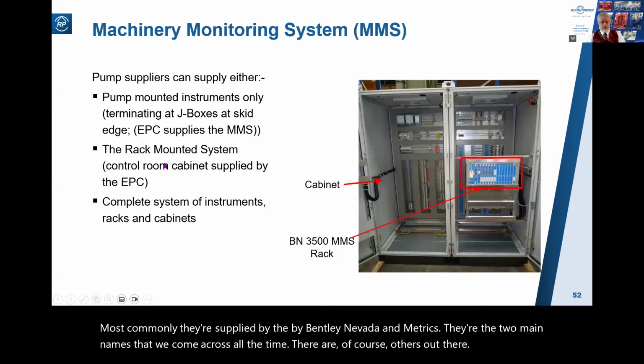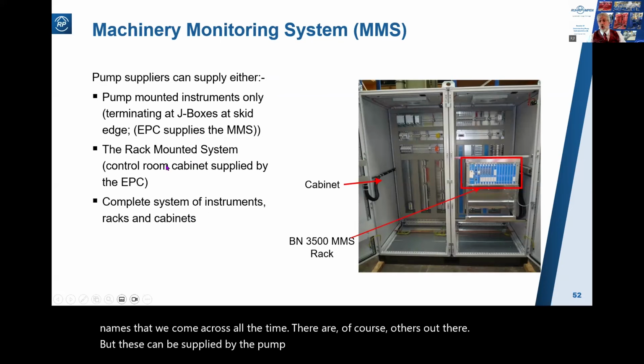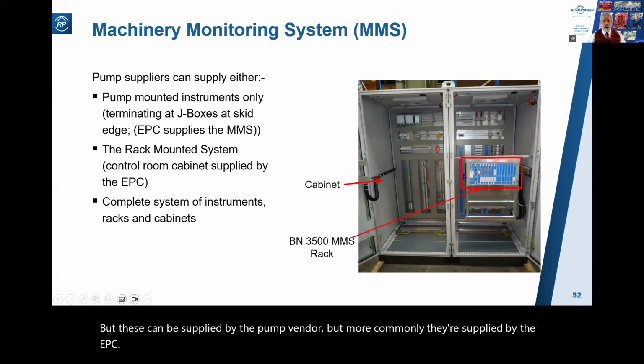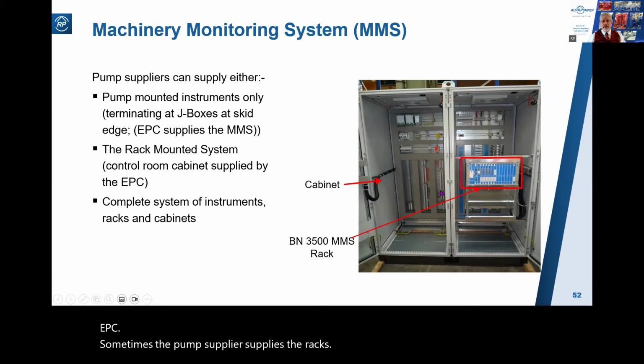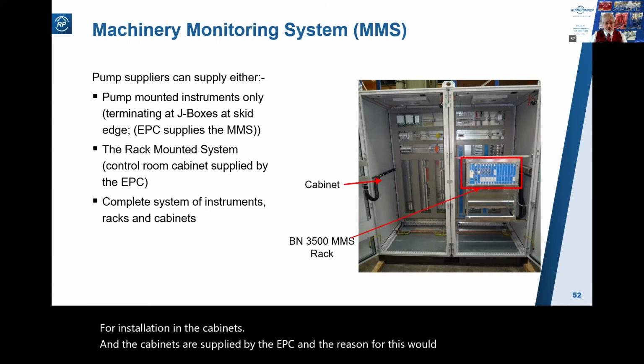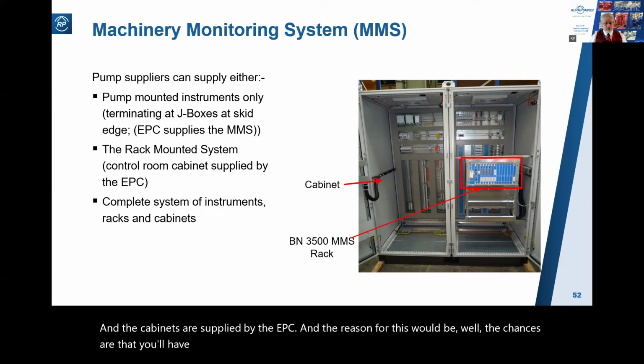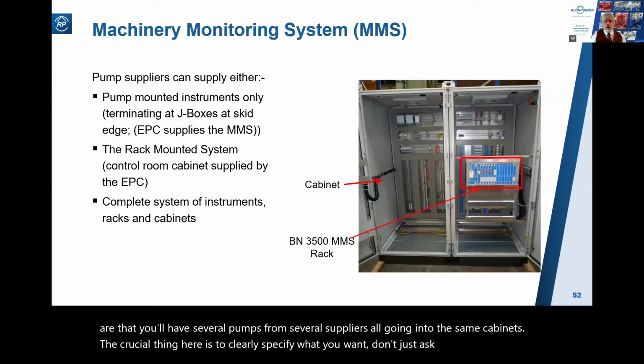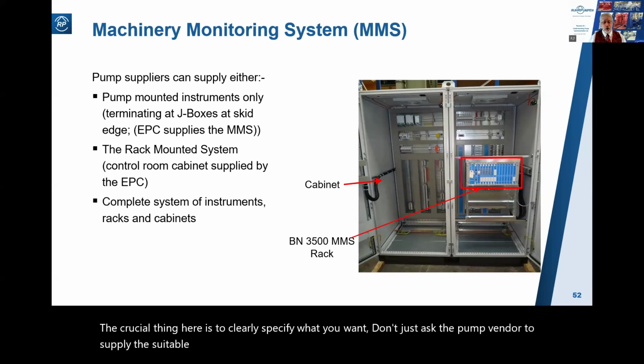But these can be supplied by the pump vendor, but more commonly they're supplied by the EPC. Sometimes the pump supplier supplies the racks for installation in the cabinets, and the cabinets are supplied by the EPC. And the reason for this would be, well, the chances are that you'll have several pumps from several suppliers all going into the same cabinets. The crucial thing here is to clearly specify what you want. Don't just ask the pump vendor to supply a suitable MMS. You don't know what you'll be getting, and it would be very hard to compare like with like.